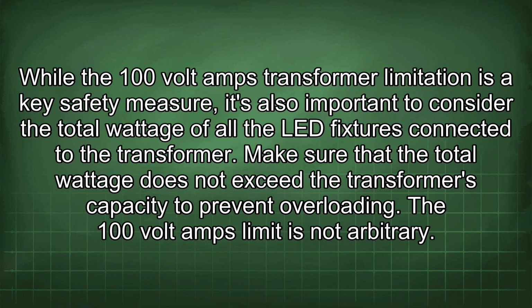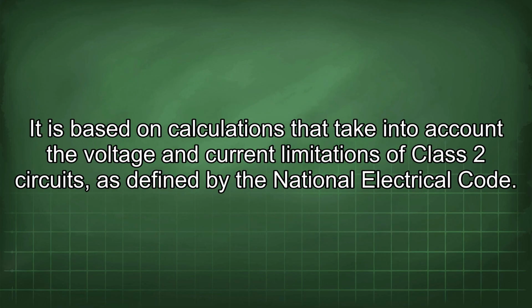While the 100 volt-amps transformer limitation is a key safety measure, it's also important to consider the total wattage of all the LED fixtures connected to the transformer. Make sure that the total wattage does not exceed the transformer's capacity to prevent overloading. The 100 volt-amps limit is not arbitrary. It is based on calculations that take into account the voltage and current limitations of Class 2 circuits as defined by the National Electrical Code.